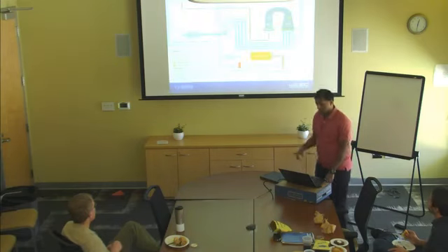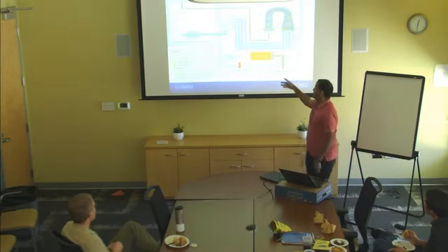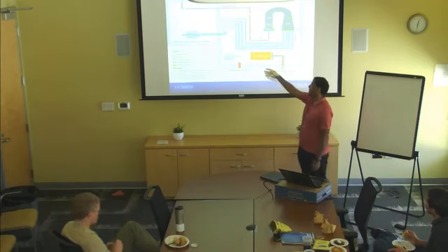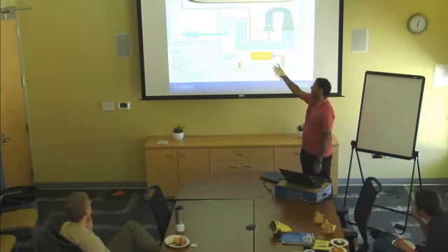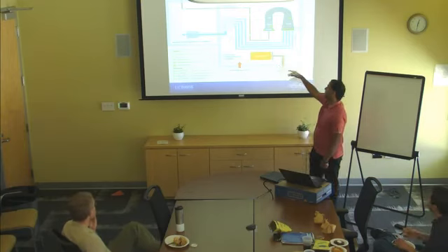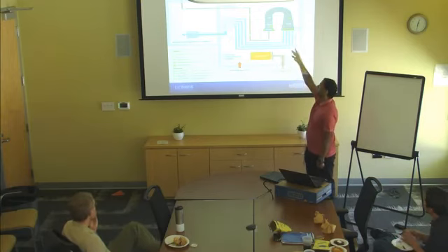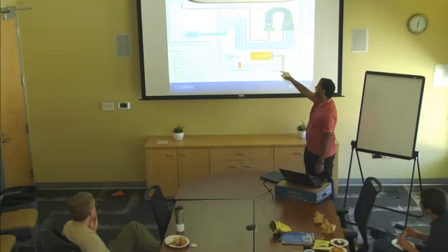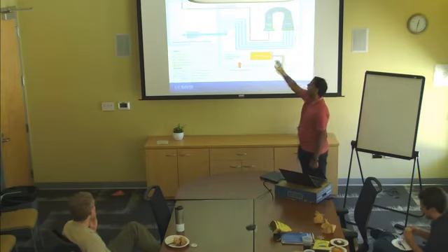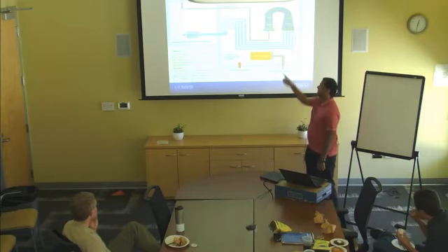Regarding the instrumentation, we measured the outdoor air temperature, which in this context is more the duct zone temperature. We measured the temperatures and pressures at the plenum and the refrigerant line, and we also measured the temperature of air leaving the grill and entering the ducts.